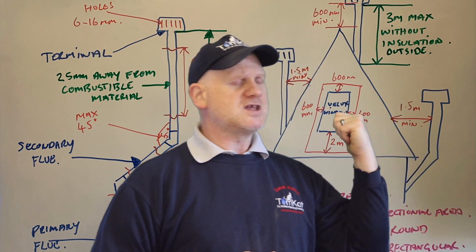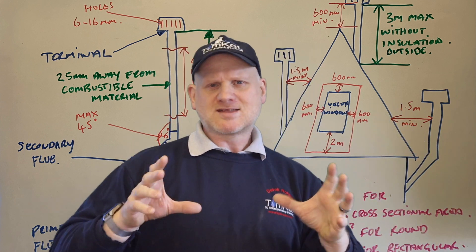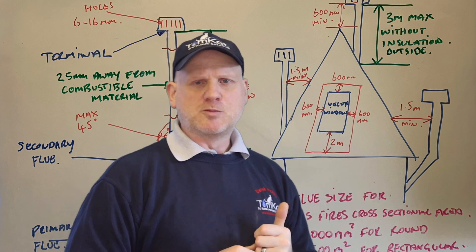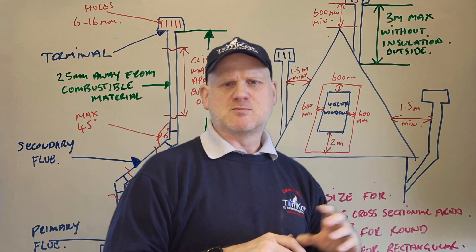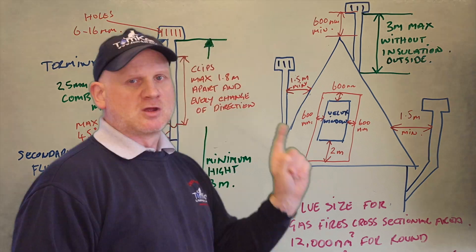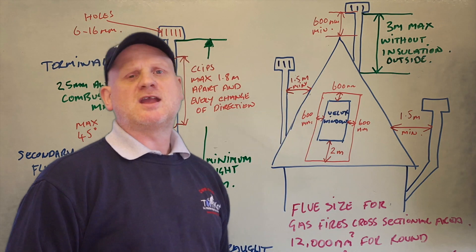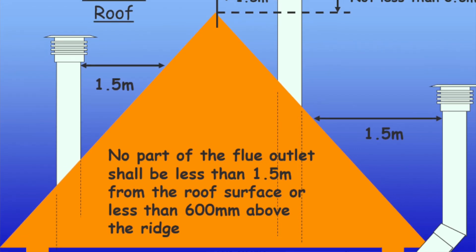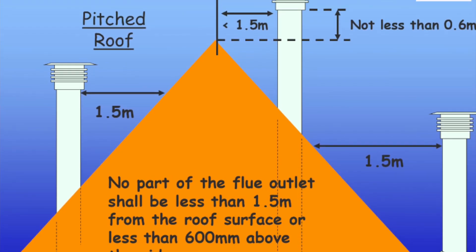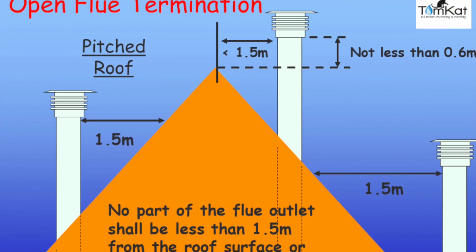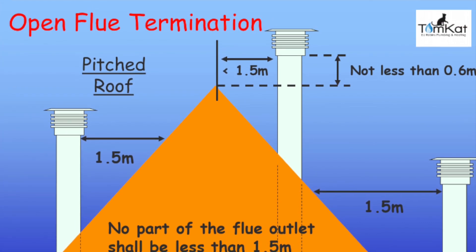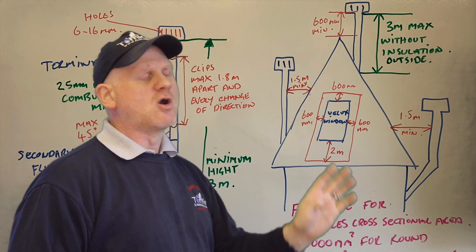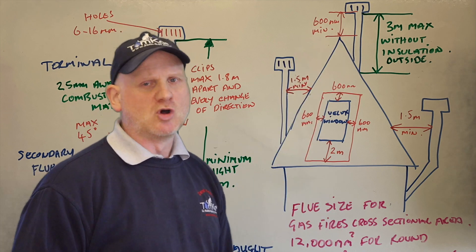When exiting the building, the positioning of the open flue pipe matters. From the side of the flue to the roof on a horizontal plane, you need more than 1.5 meters away. At the top, the terminal needs to go above the ridge by more than 600mm.